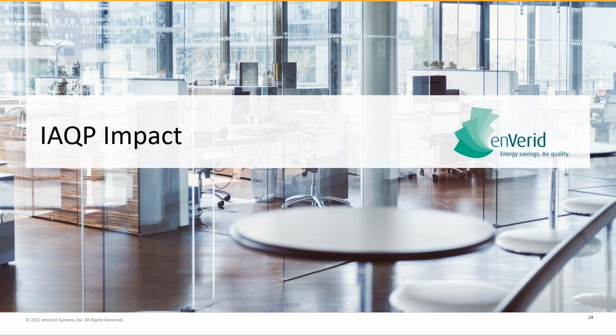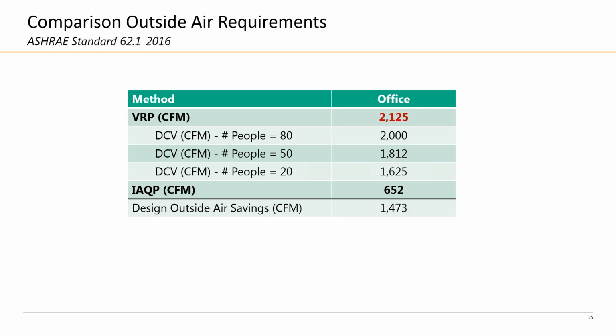Thanks. Excellent. Thank you. With respect to IAQP, let's take a look at the impact of what IAQP does versus ventilation rate procedure. In a standard office building in this particular case, you might require 2,125 CFM of outside air. If you deploy CO2 sensors within the space that only need to be calibrated once every 5 years, you could use demand control ventilation as a barometer for occupancy and drive down that outside air. But since demand control ventilation has a fixed component surrounding square footage, the benefit of demand control ventilation floors out at about 30% below ventilation rate procedure.